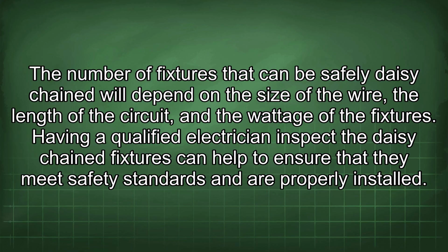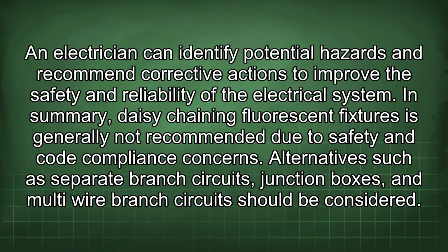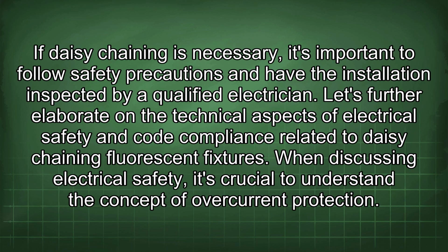Having a qualified electrician inspect the daisy-chained fixtures can help to ensure that they meet safety standards and are properly installed. An electrician can identify potential hazards and recommend corrective actions to improve the safety and reliability of the electrical system. In summary, daisy chaining fluorescent fixtures is generally not recommended due to safety and code compliance concerns. Alternatives such as separate branch circuits, junction boxes, and multi-wire branch circuits should be considered. If daisy chaining is necessary, it's important to follow safety precautions and have the installation inspected by a qualified electrician.